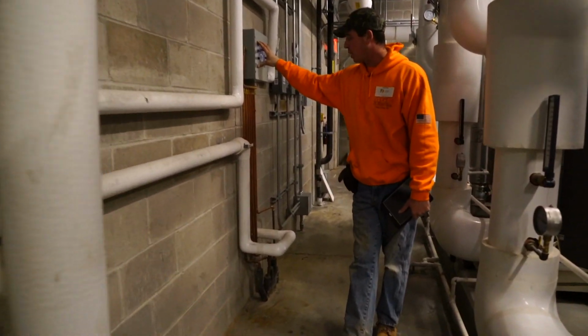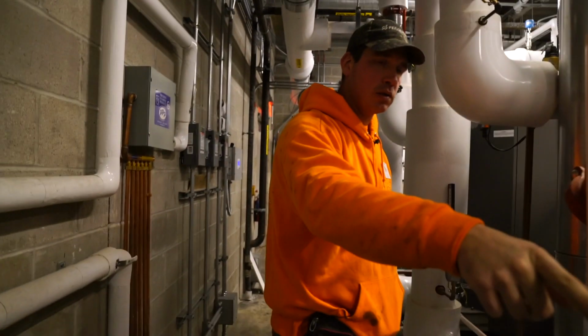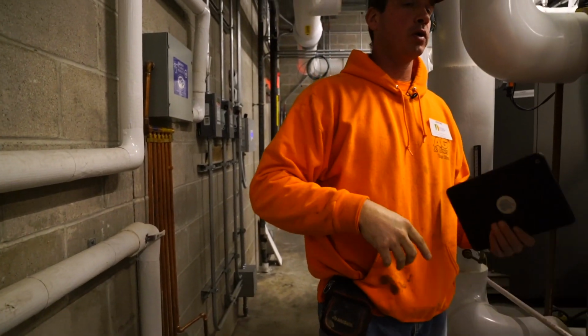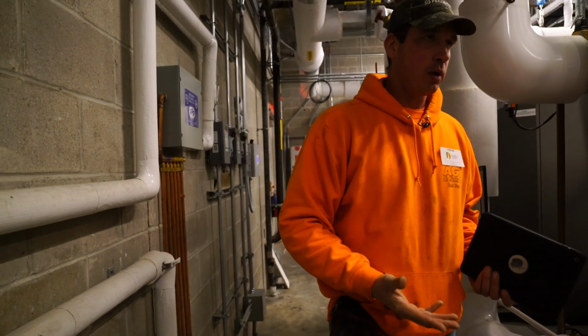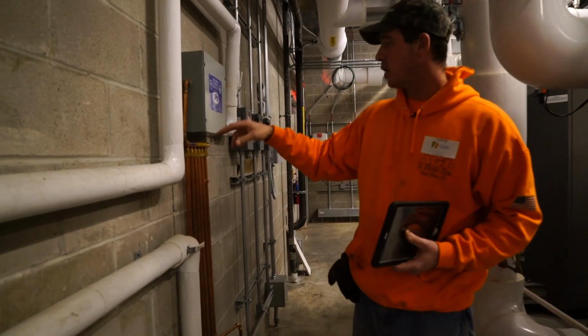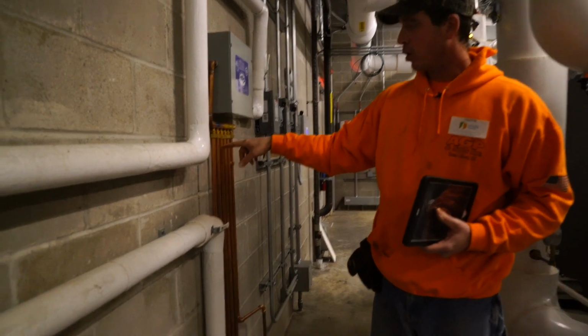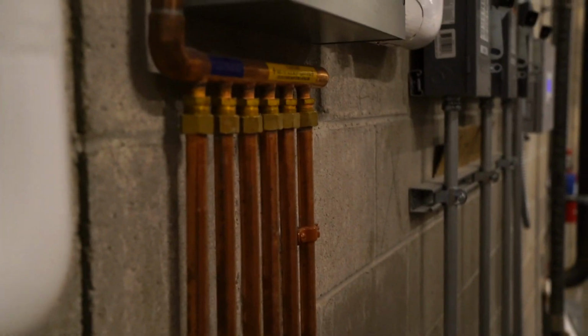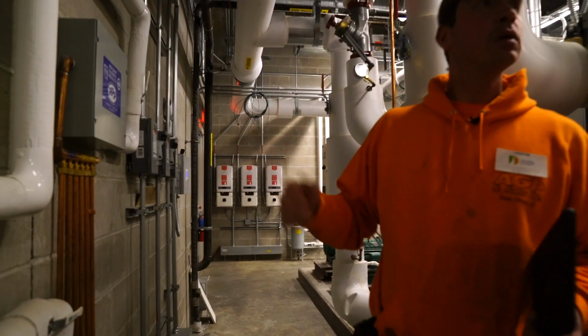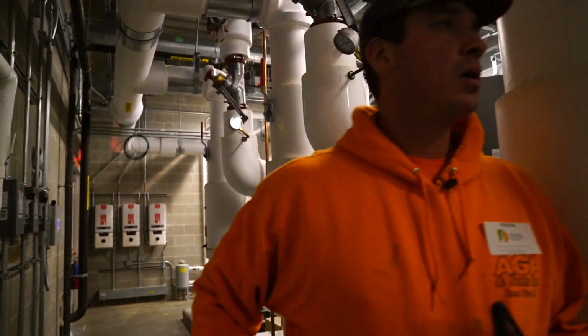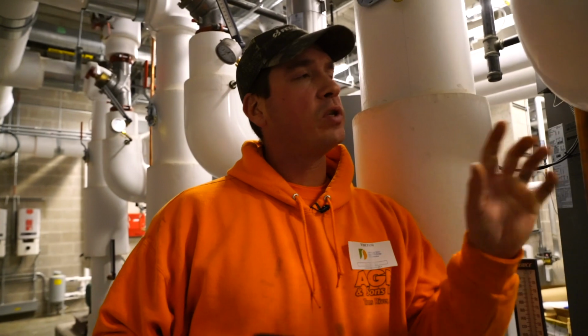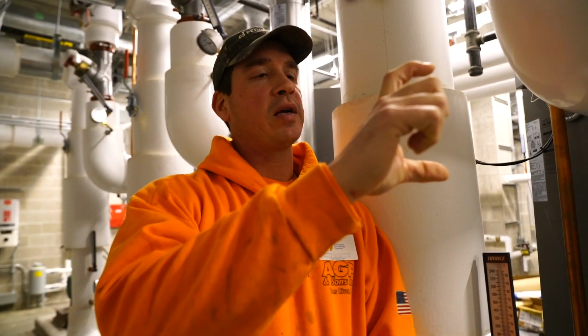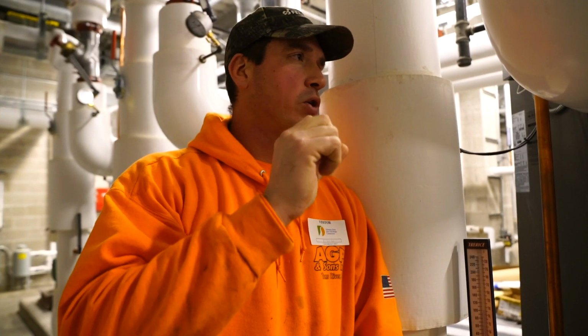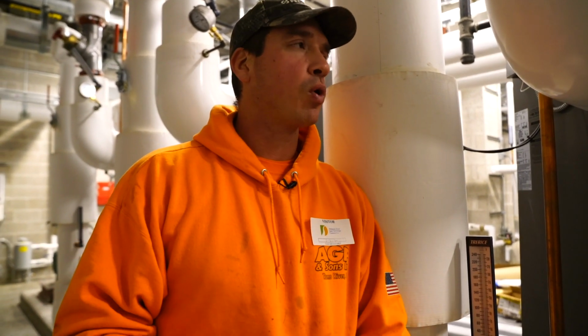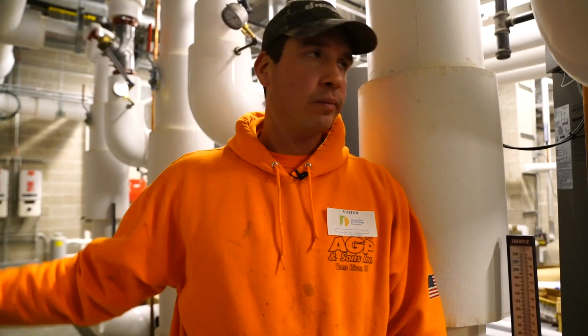This is a trap primer box. Basically all the floor drains that you see in the mechanical room, just because they're never gonna accept any water in here really, so the traps don't dry up. This is an automatic system where there's water always kind of dripping down these lines into the traps, so they always have water in them. Is that same system in the other mechanical room too? Yes, yes. Basically, even the ones in the bathroom overhead have them. They're just little brass fittings in the bathrooms, and they just drip water into the floor drains, just so they're always primed. This one, since it's feeding multiple, it's an electronic device.